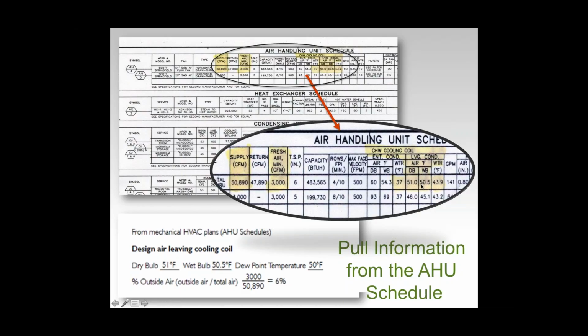If we find out that the leaving air dry bulb is 51 degrees and the wet bulb condition is 50.5 degrees, going back to the psychrometric chart, we can run a calculation and find that the dew point temperature for those two conditions is 50 degrees. So this cooling coil that serves a storage space within an institution is actually only meant to create a 50-degree dew point for us, which means that any set point conditions, any temperature, any preservation goals that we set are going to be specifically and very distinctly influenced by that dehumidification capacity. With a 50-degree dew point, we're going to have a hard time keeping cool temperatures in there in order to slow the rate of chemical decay.